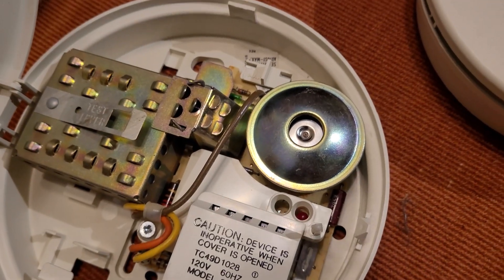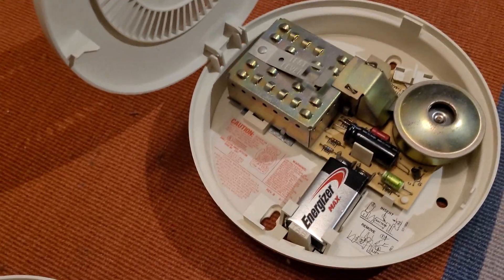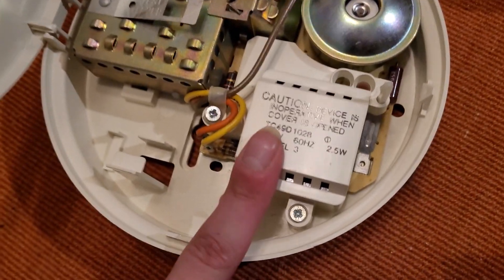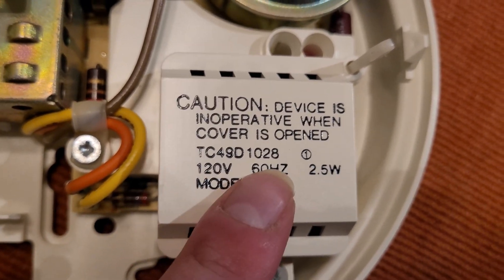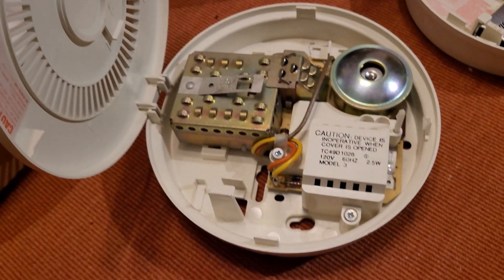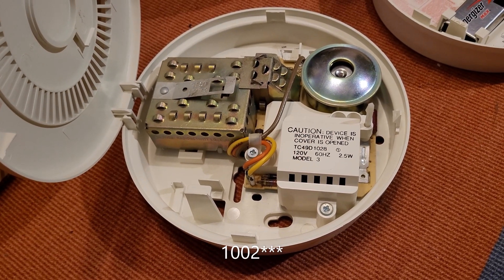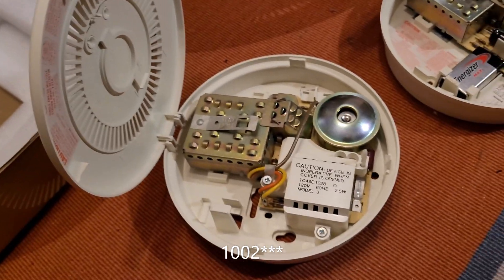It's basically just like the CD200A — the regular Kobishi CLB27 squealer horn and the same exact sensor. The only difference is that this one has the onboard transformer. This one is catalog number TC490 1028. There was another version — I was completely wrong — the version that doesn't have interconnect is the 1002.